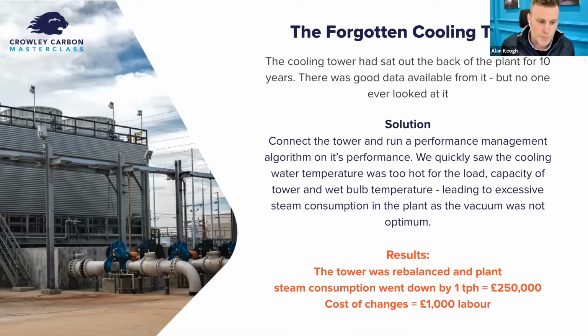So when we hooked it up, ran it through our algorithms, and figured out it was not meeting performance, we went to investigate it. As it turned out, it was just a simple balancing issue on the cooling tower. So we rebalanced the flow over the top of the tower, which stopped short circuiting from happening, and we dropped the water temperature coming out by about 4 degrees.